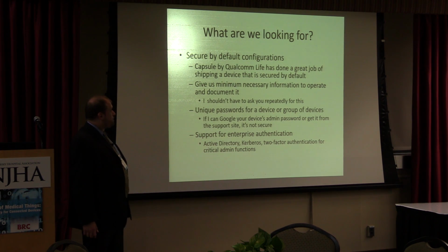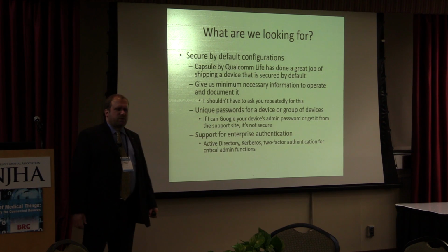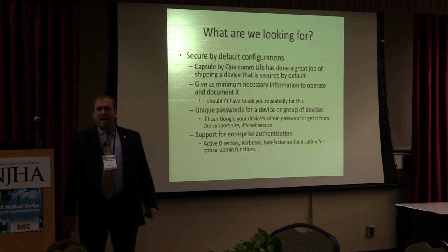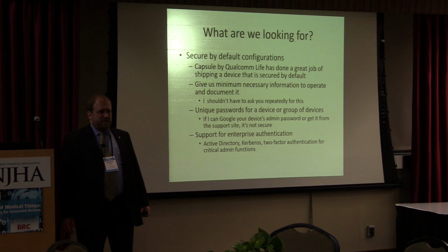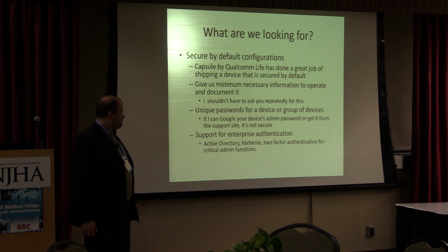And unique passwords for a device or group of devices. There's one other thing I'm well aware of. I can Google and find most medical device passwords, and I've done it. I've actually had 1 or 2 cases where I've had to get into a device and didn't know the default password, I Googled. I got in.